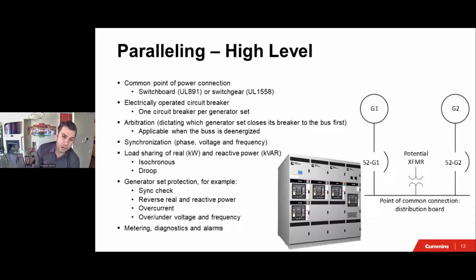We need to have some kind of arbitration if I have a fleet of 2 or more, or 17, gensets and they're all ready to close and connect to this bus right here, to this common point of connection. We need to determine, arbitrate, which one closes to the bus first.